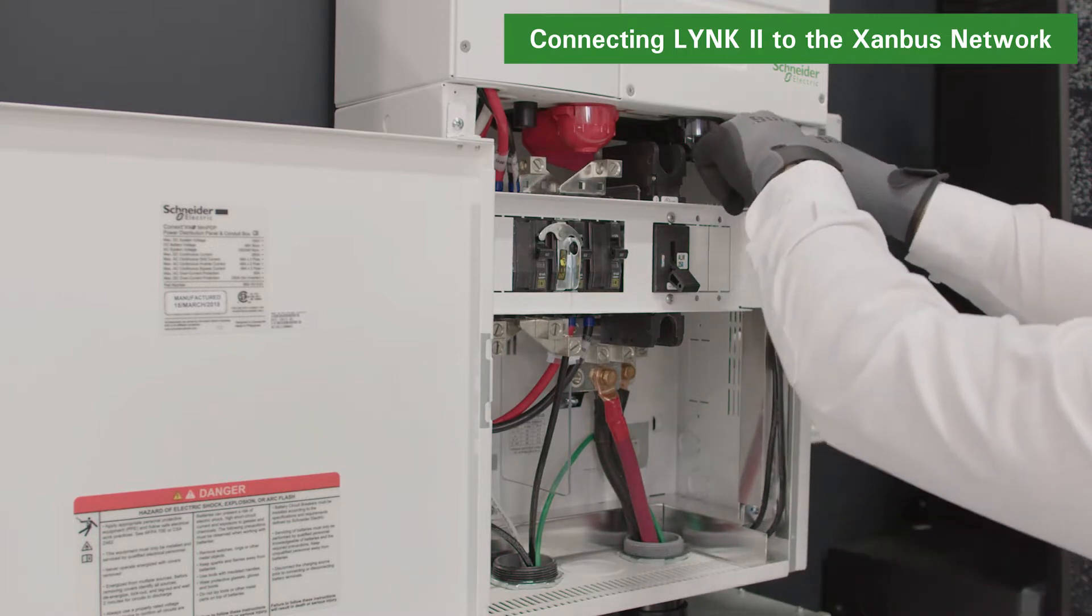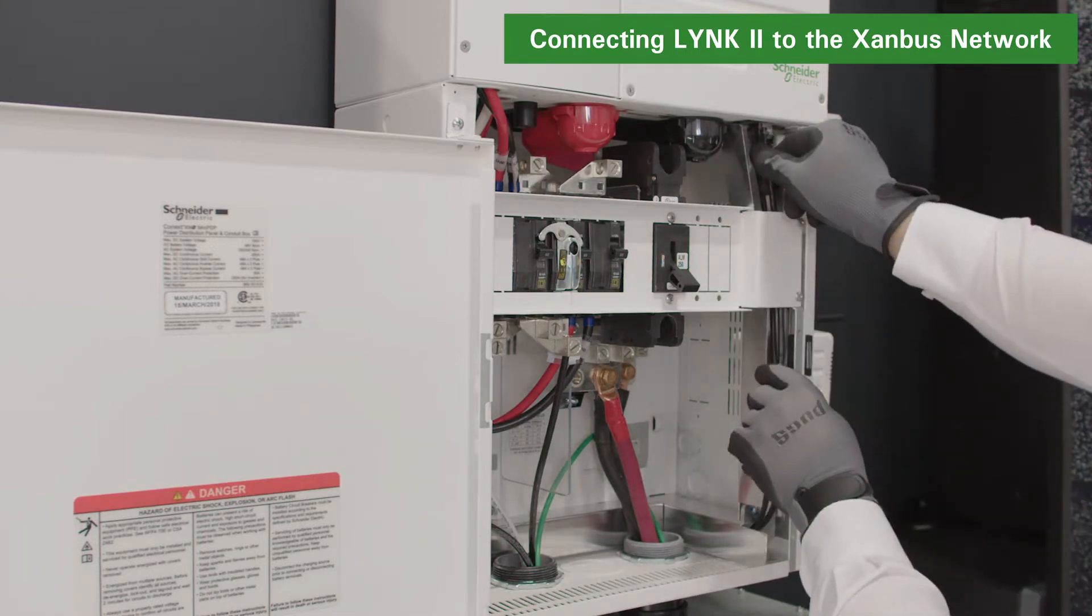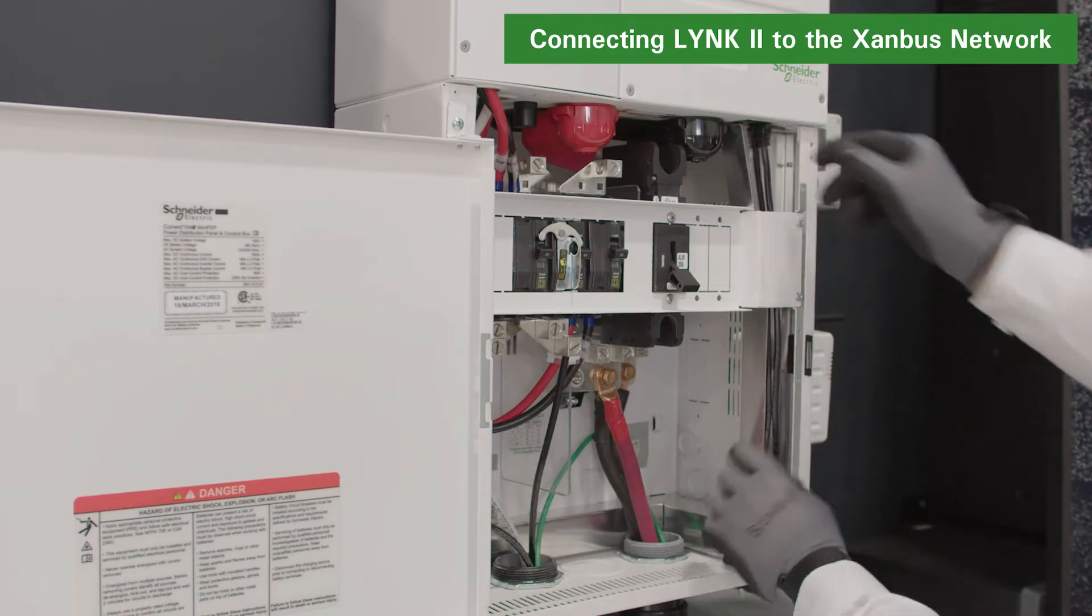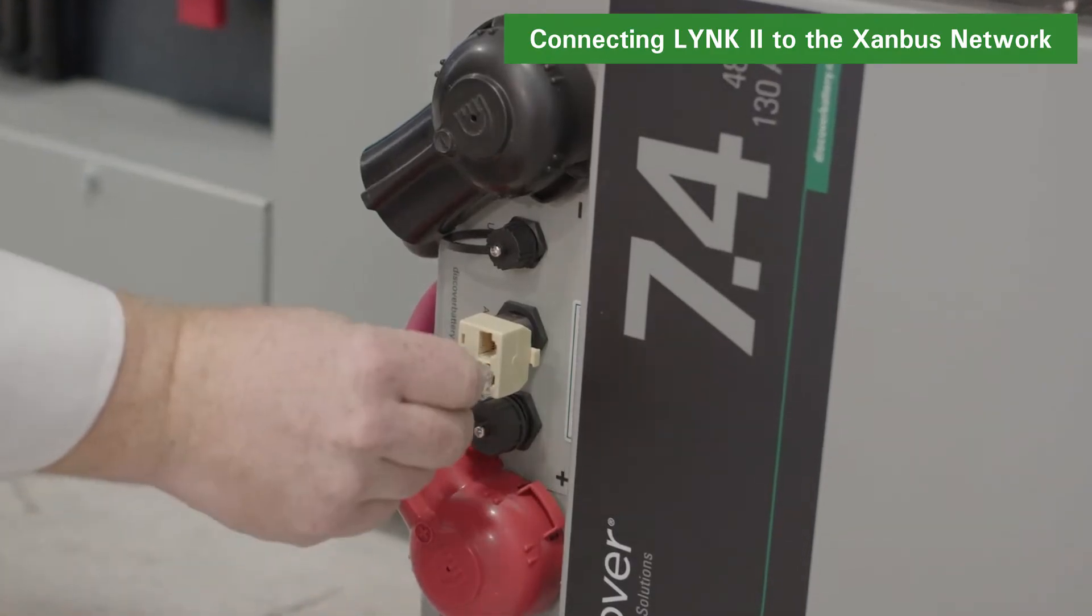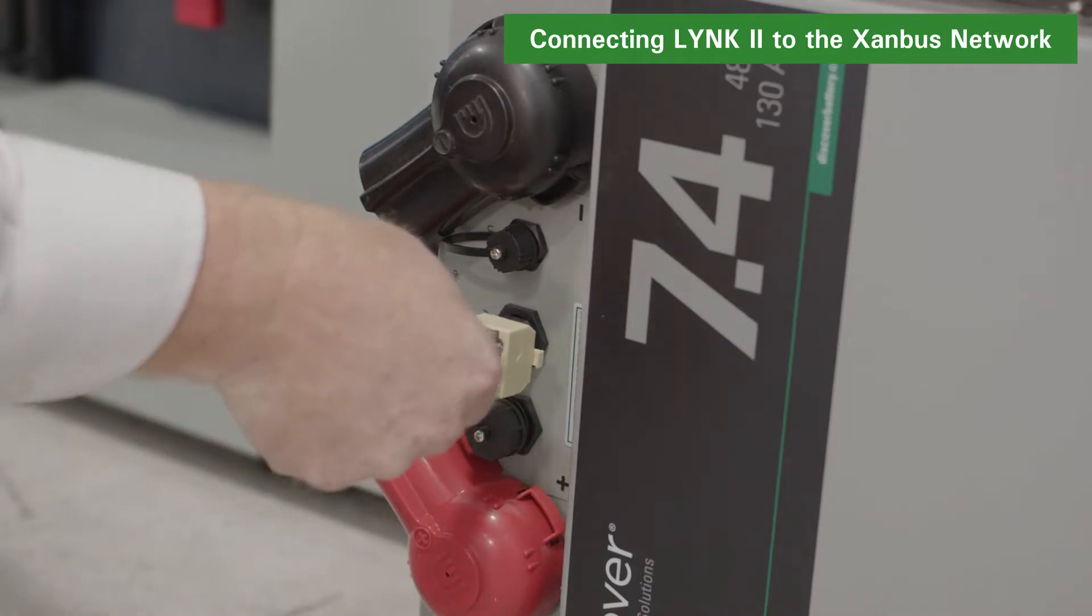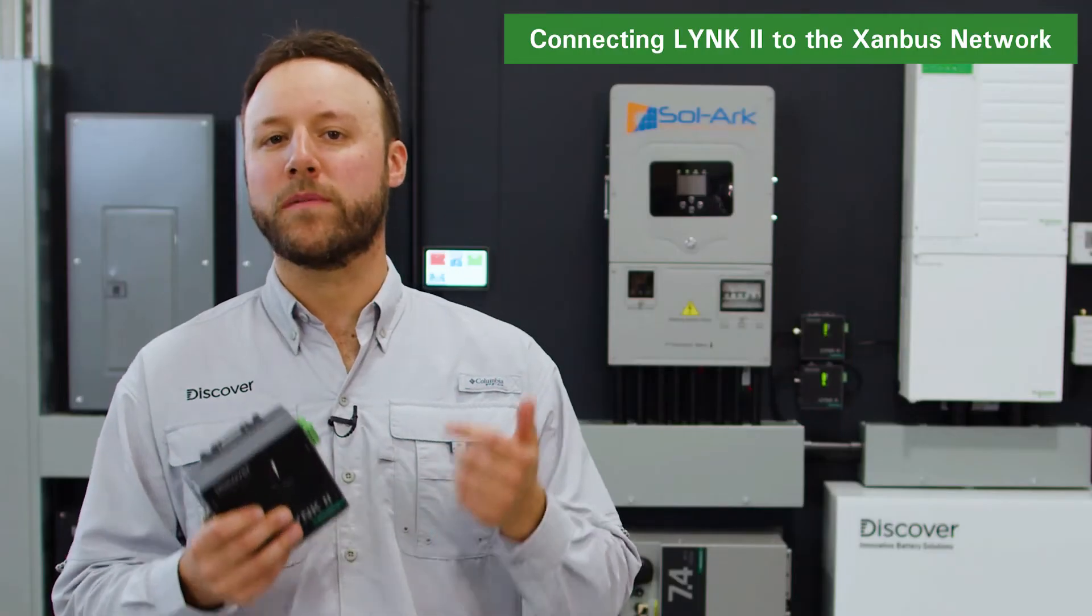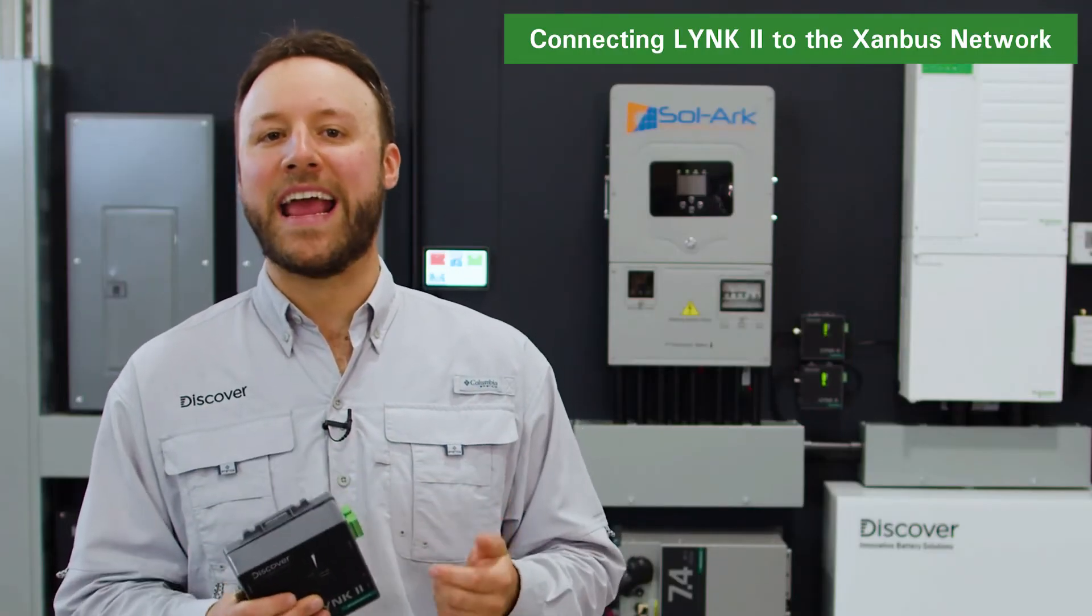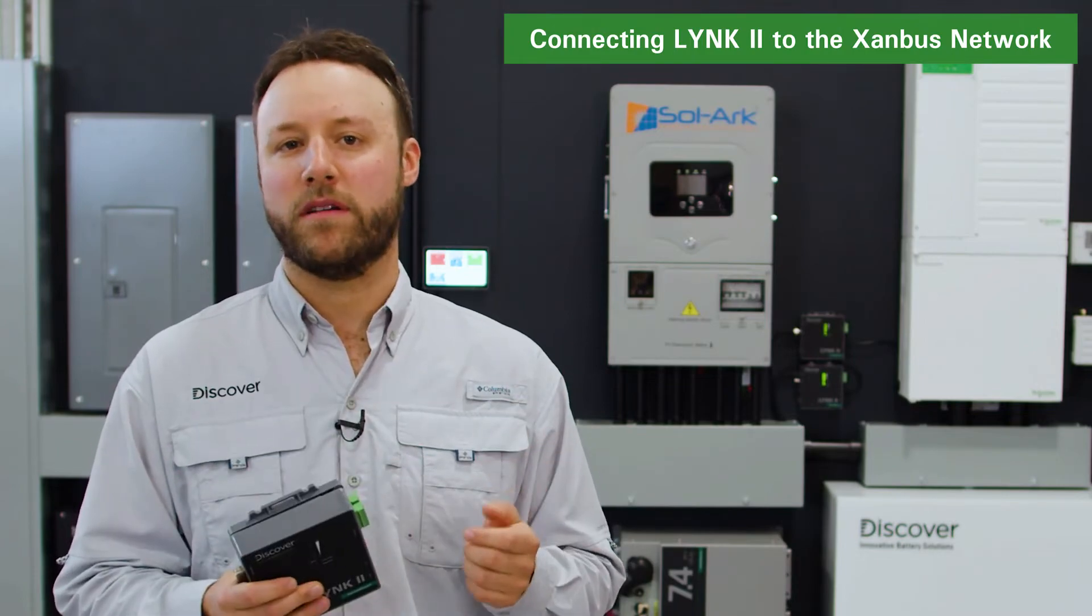At the other end of the Xanbus network, use the Insight-Home device to terminate the network. Ensure that both the battery and Xanbus networks are correctly terminated. The LYNK II will terminate one end of each battery and the Xanbus network.